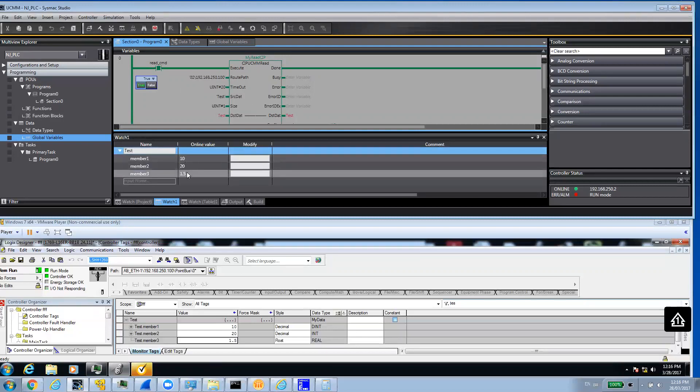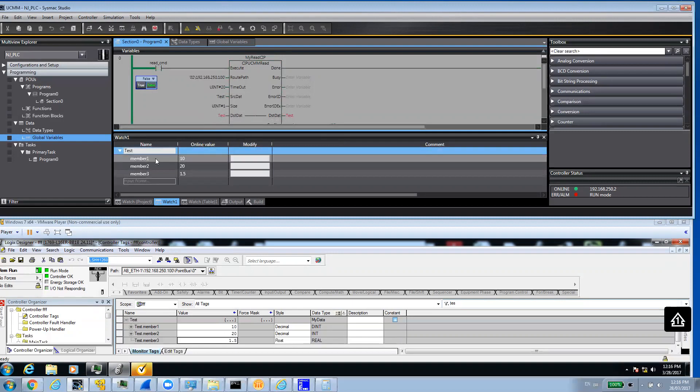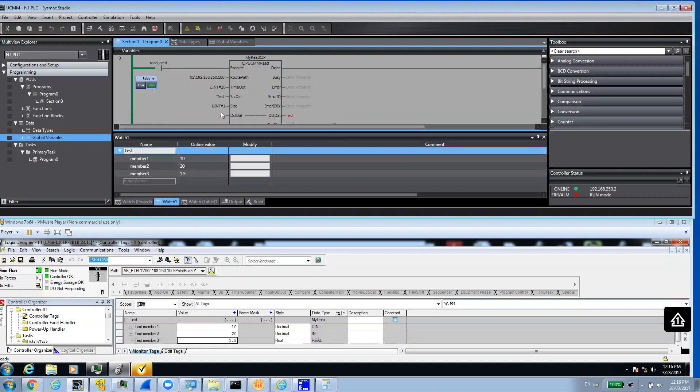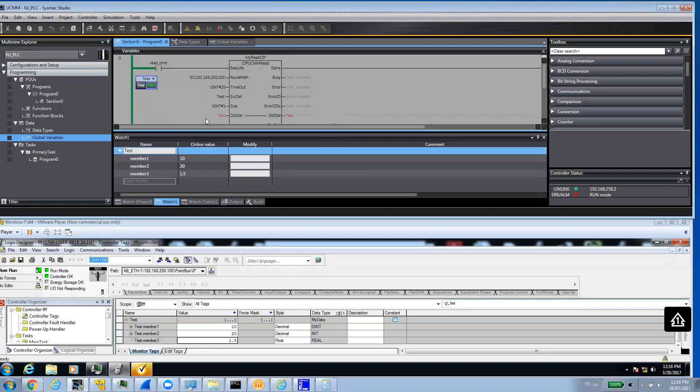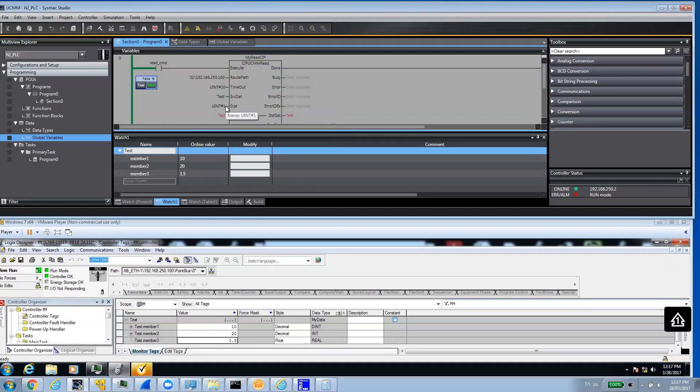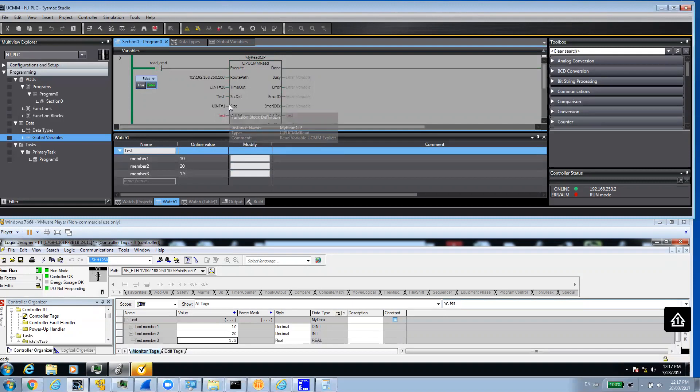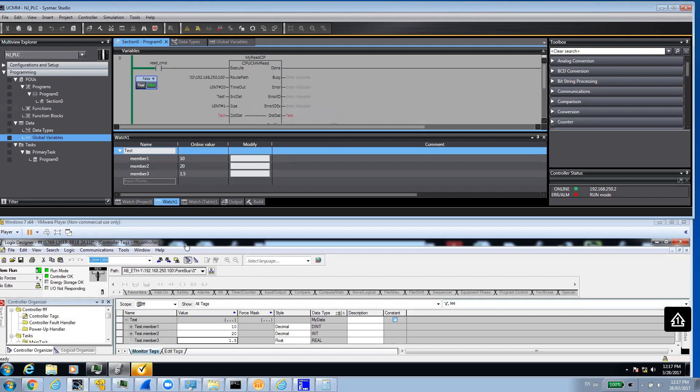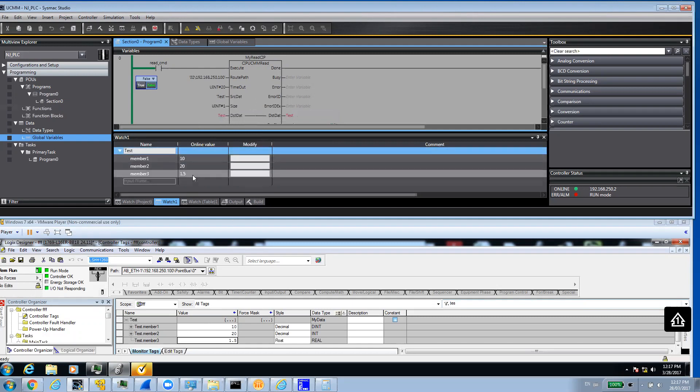It's really done. And I read my variables. Now, notice here I didn't change also the size. Don't get confused. Although we have three members here of this structure, but it's still considered as one element. Because it's just one structure. It's still considered as one tag. Now if we have an array of this structure, let's say an array of four or five, then you will need to specify here that you have four or five arrays you want to read from the other PLC. But if it's one, although you have a few members in that structure, it's still considered as one. Because you can look at it in one shot.